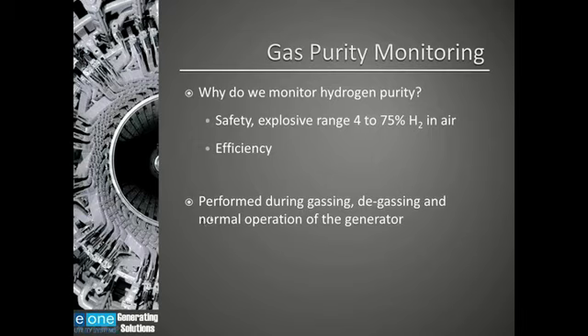We also want to measure gas purity during the degassing and gassing of the generator. We want to make sure that we get all the air out of the unit before we put CO2 and hydrogen in there. We want to make sure that we get all of the hydrogen out before we put air in the generator. And as we said here, we want to measure the hydrogen purity during normal operation of the generator.